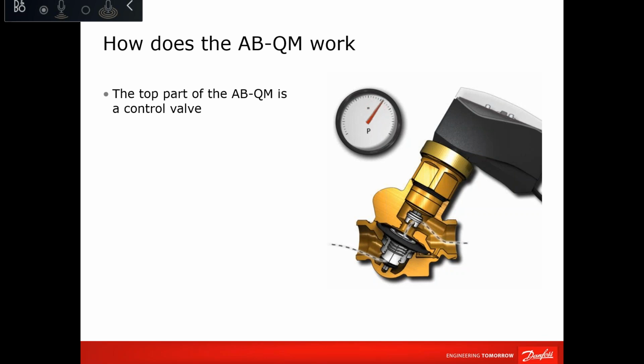Okay. And next, what are the advantages of Danfoss PICV compared to other PICVs or other brands available in the market? I would name a simple advantage: we have our own valve and actuator, and we have the combination itself of the valve. Let's say most PICV manufacturers have either the valve or the actuator, and they outsource the other one. In our case, the valve can be used as linear and equal percentage. The valve has full authority at any setting, and you cannot find this anywhere else.